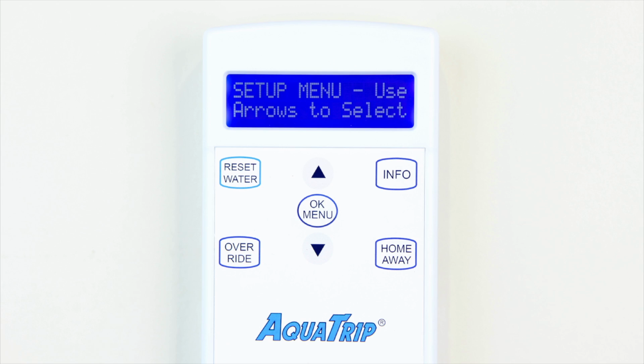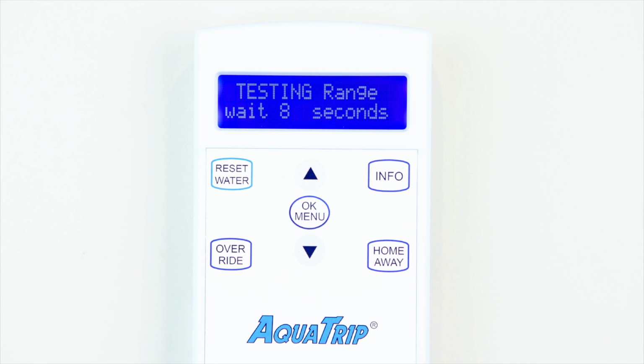Now press Menu OK on the control panel and scroll through to the radio range test menu. Then press OK. The control panel will now detect the signal from the control unit every 15 seconds and indicate the signal strength as a percentage. Start by standing next to the shutoff valve for the first reading and then walk towards your desired control panel mounting position, retesting as you go.